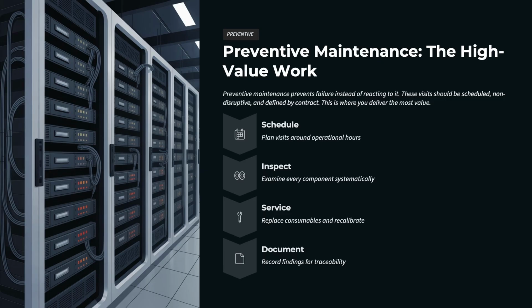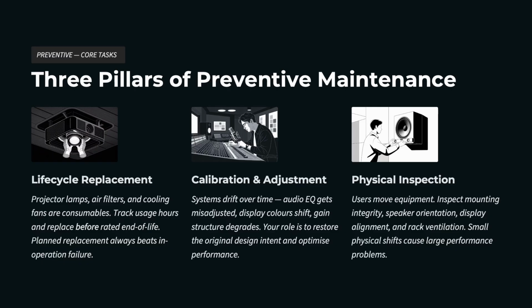A few core preventive maintenance tasks: first, life cycle based replacement. Some components are consumables, such as projector lamps, air filters, and cooling fans. Best practice is to track usage hours and replace before rated end of life, adjusting schedules based on real-world conditions. Failure during operation is always worse than planned replacement.